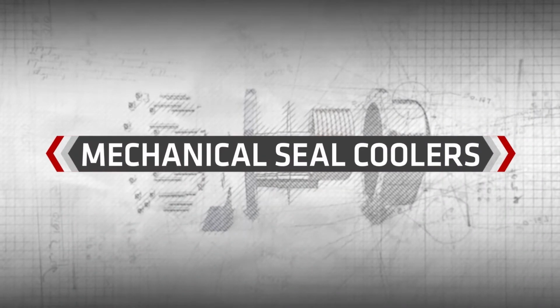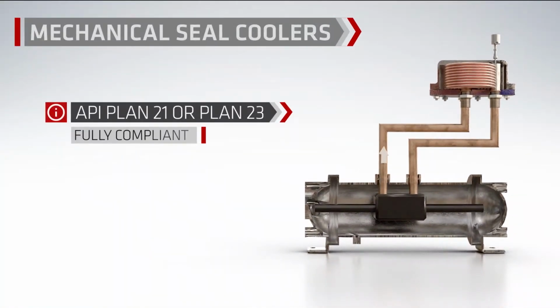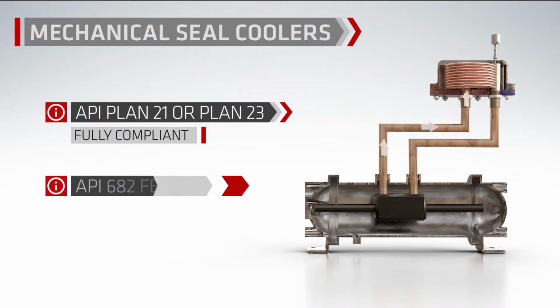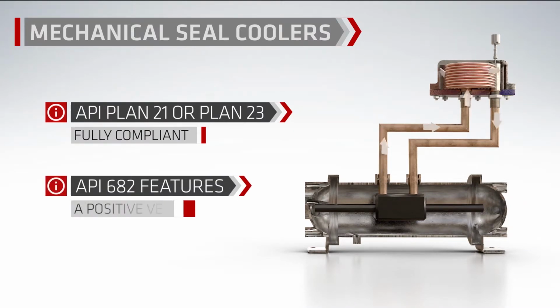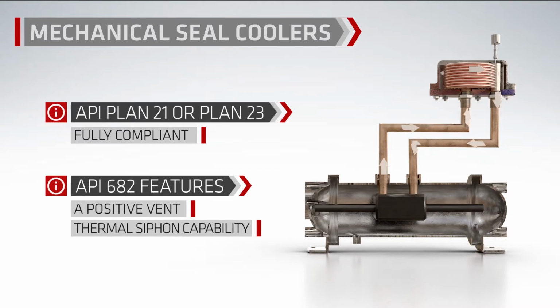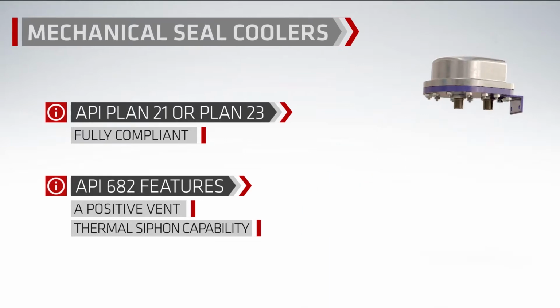The Heliflow is most often used in Plan 21 and Plan 23 applications in accordance with API Standard 682 for pump seal coolers. API 682 requires that the heat exchanger have a positive vent and have thermal siphon capability, both of which the Heliflow heat exchanger can provide.